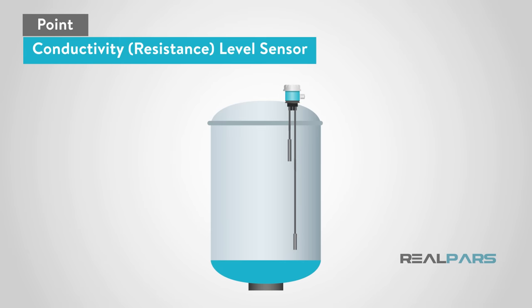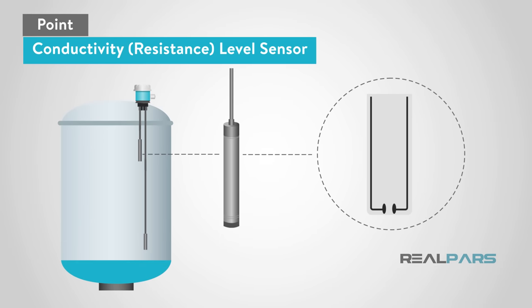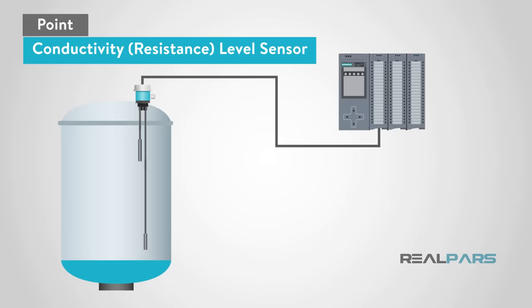Another style of point level sensor is conductivity or resistance. A conductivity or resistance sensor uses a probe to read conductivity. The probe has a pair of electrodes and applies alternating current to them. When a liquid covers the probe, its electrodes form a part on an electric circuit, causing current to flow, which signals a high or low level.